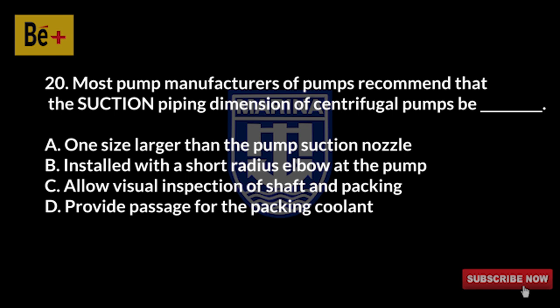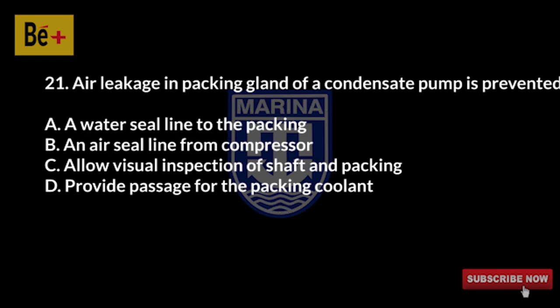Most pump manufacturers recommend that the suction piping dimension of centrifugal pumps be: A) one size larger than the pump suction nozzle, B) installed with a short radius elbow at the pump, C) allow visual inspection of shaft and packing, D) provide passage for the packing coolant. The answer is A, one size larger than the pump suction nozzle.